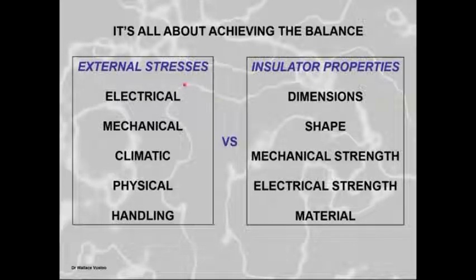So you need to take a look at what the insulator is subjected to electrically, mechanically, the climate, the actual physical size and the handling and so on of the insulator, and then you take those external stresses which the insulator is subjected to handling. The majority of damage to insulators today is due to poor handling, transportation, and installation practices. The guys damage the insulator before it is actually even energized. So one of our biggest external stresses is just the scenario of handling it.